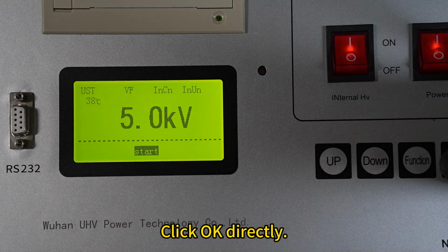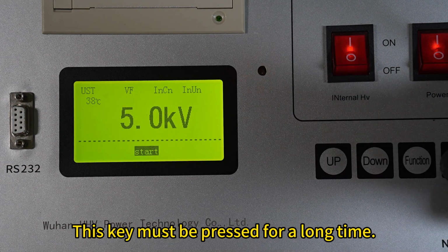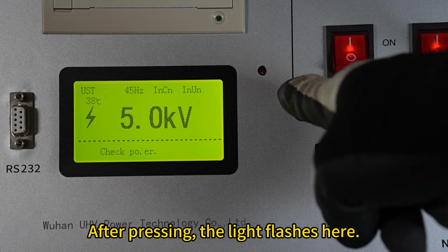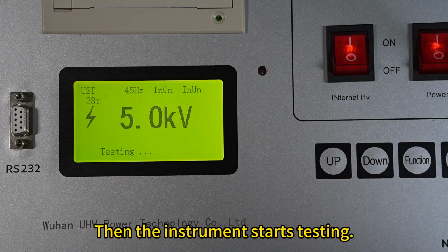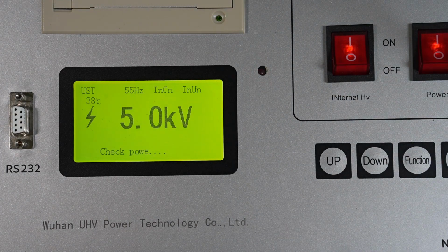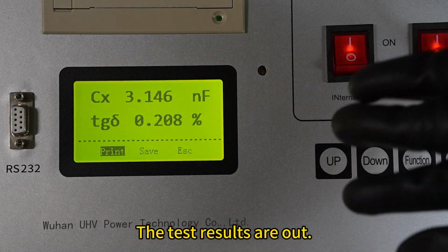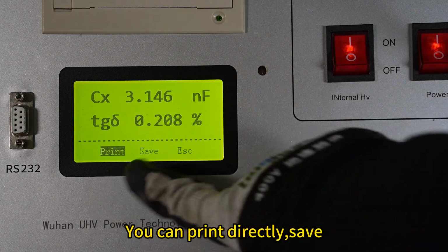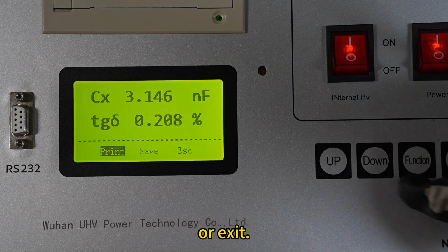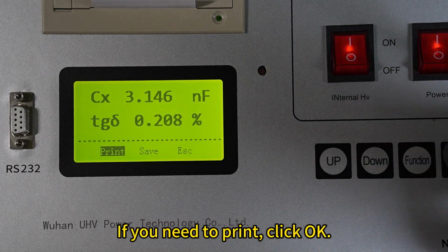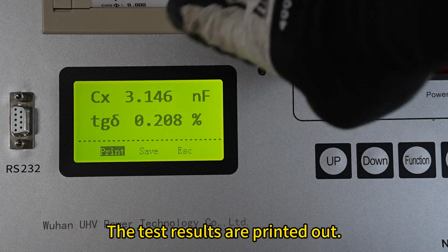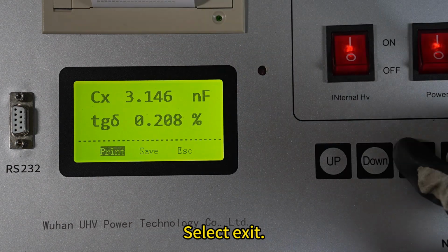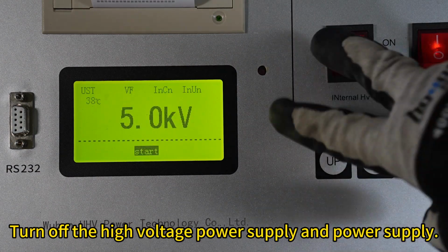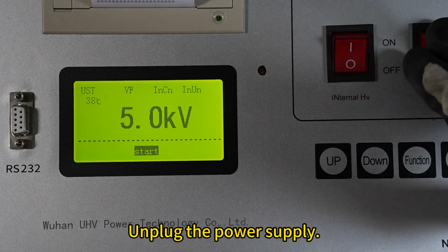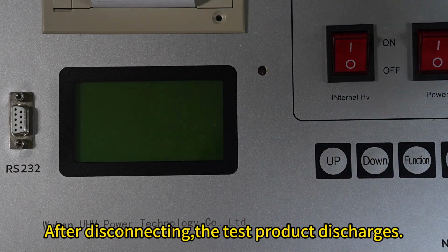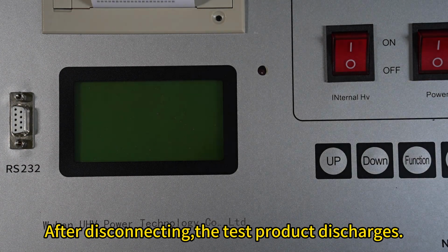Click OK directly. This key must be pressed for a long time. After pressing, the light flashes here. Then the instrument starts testing. The test results are out. You can print directly, save, or exit. If you need to print, click OK. The test results are printed out. Select Exit. Turn off the high voltage power supply and power supply. Unplug the power supply. After disconnecting, the test product discharges.